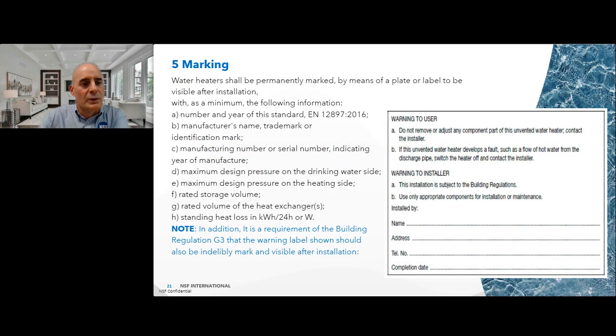Section 5 is the marking requirements. Water heaters should be permanently marked by means of a plate or a label to be visible after installation. As a minimum, the following information: number and year of the standard, manufacturer's name, trademark or identification mark, manufacturing number or serial number indicating the year of manufacture, maximum design pressure of the drinking water side or the secondary circuit, and maximum design pressure of the heating side or the coil or coils.